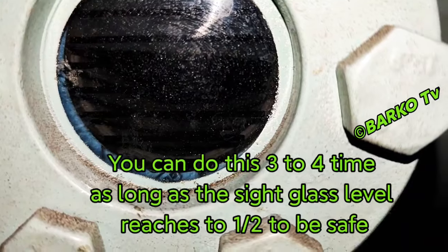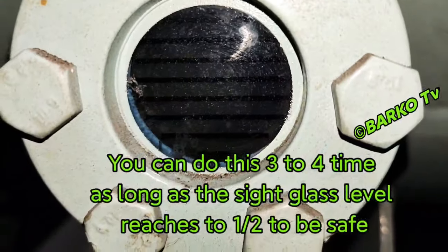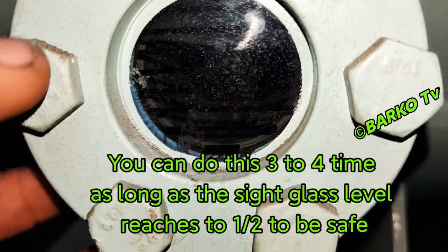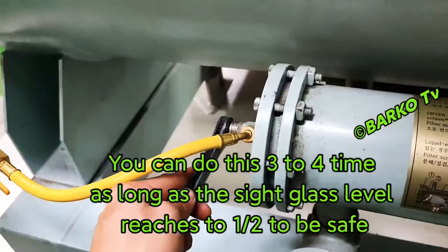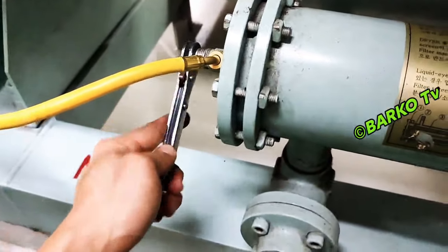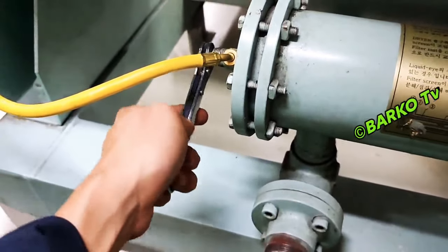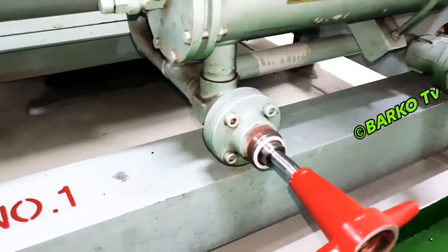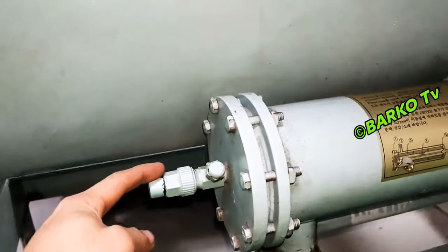Do this 3 to 4 times to ensure the level at the receiver is at half to be safe. Start, stop about 3 to 4 times until the level of the sight glass is at half to be safe. Okay, and then close the liquid charging valve. Much better if on the last cycle you close the bottle and then the compressor sucks so that there is no refrigerant in the hose. After that, open this valve, already open, and then secured.